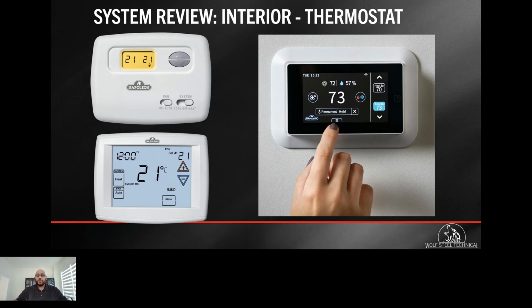A smart thermostat will consider all the equipment that is installed, using information like an outdoor temperature sensor, humidity, and utility costs, and it can determine the most efficient way to heat your home. As an example, if the outdoor temperature is negative 20 degrees Celsius, the thermostat might not even kick in the heat pump, as it may be cheaper to run your backup heat based on your utility costs.